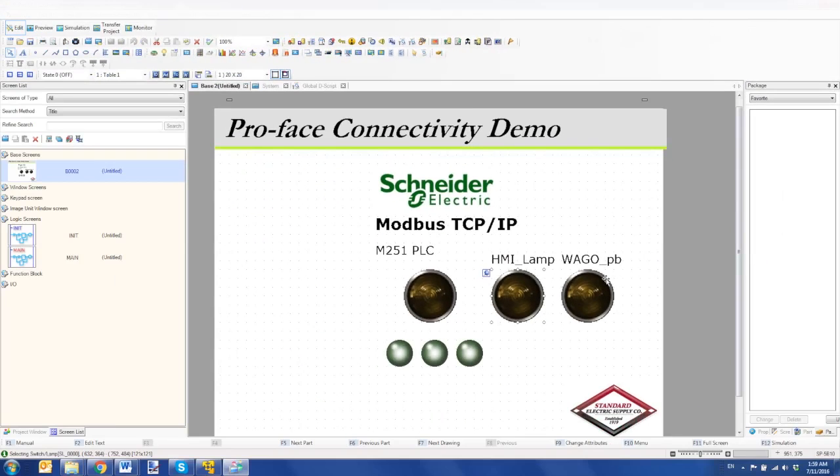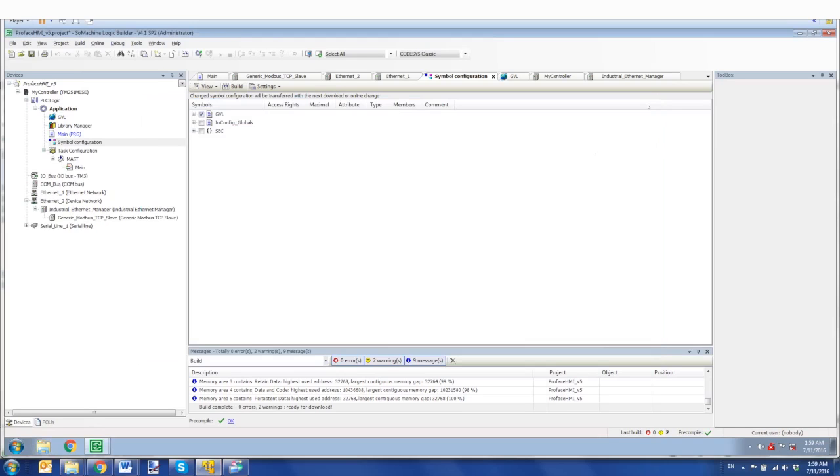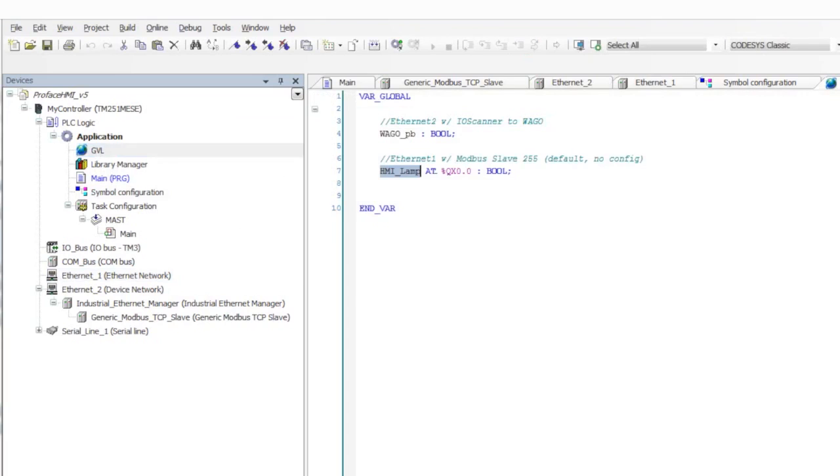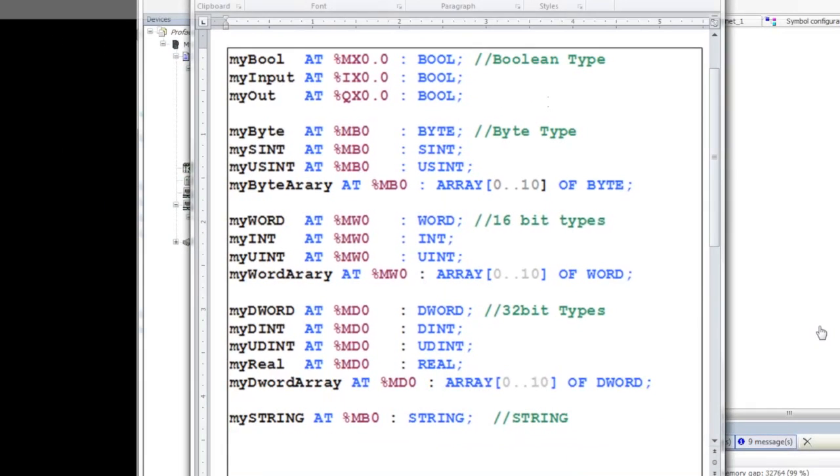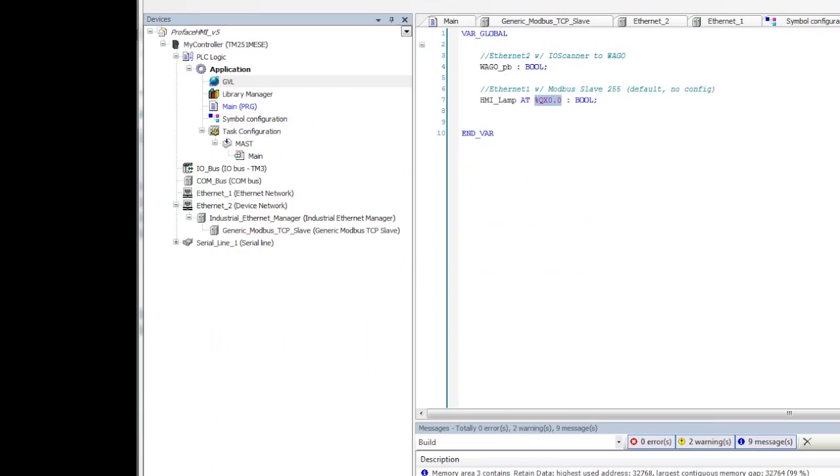Now on the Schneider side, it's important to note some of the settings. I'll jump over here to Ethernet 1. This is using the Modbus server out of the box as active. And in order to leverage that, you have to declare them in your variable declarations. And that's done by this HMI lamp at QX0. I'm sending it as an output QX0.0. Now the declarations look like this. This is an example of how you would declare variables. Now once you declare that variable, you still need to share it. And that's again through the symbol information.